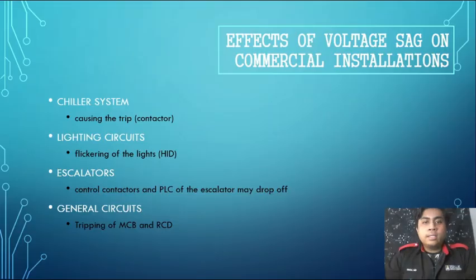Then this is the effect of the voltage sag on commercial installations. First is the chiller system, causing the trip of the contactor. Lighting circuits show flickering of the lights. For escalators, control contactors and the PLC of the escalator may drop off. And finally, general circuits see tripping of MCB and RCD.